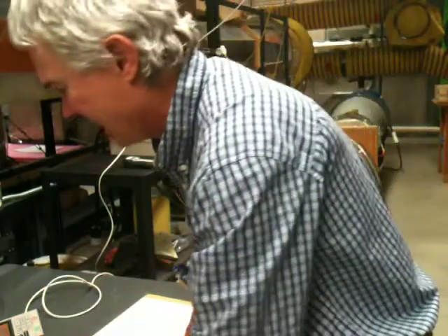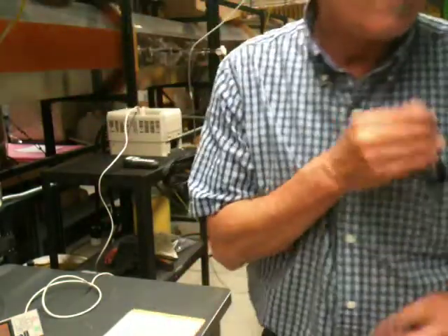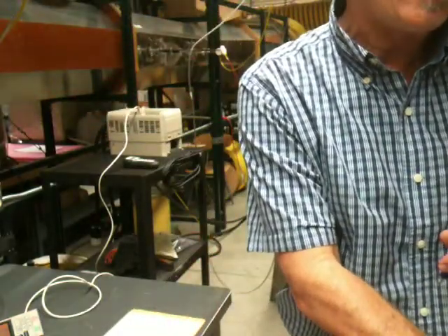Okay, it looks like the fan has ramped up to speed, and we can begin taking data. As you can hear, this fan is much quieter than the 10 horsepower fan was. This fan gets up to about 1188 RPM max, whereas the 10 horsepower fan will actually spin up to 4000 RPM. For the low speed fan test here, we are running at about 780 RPM.